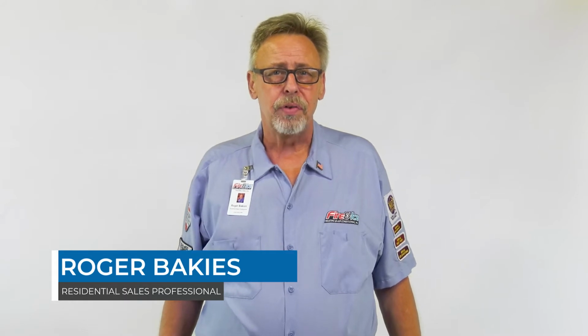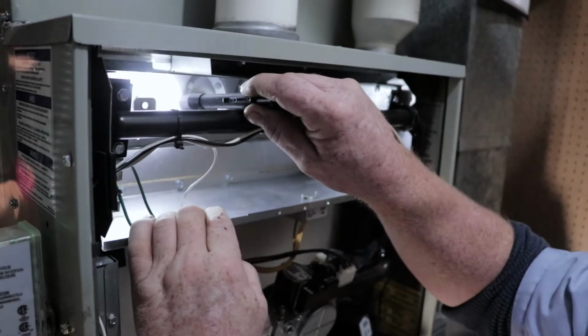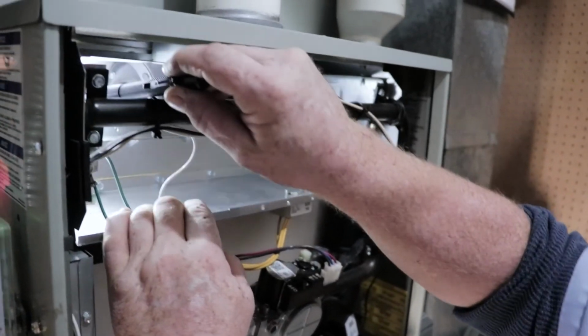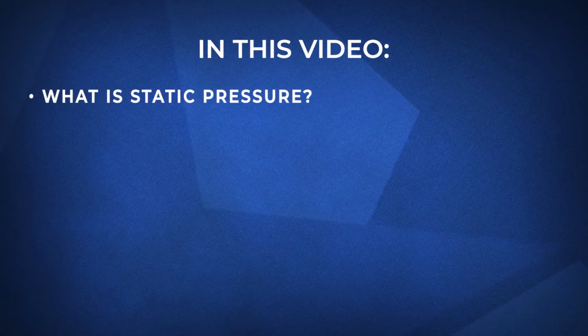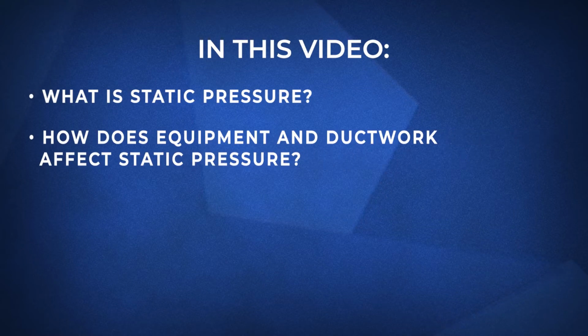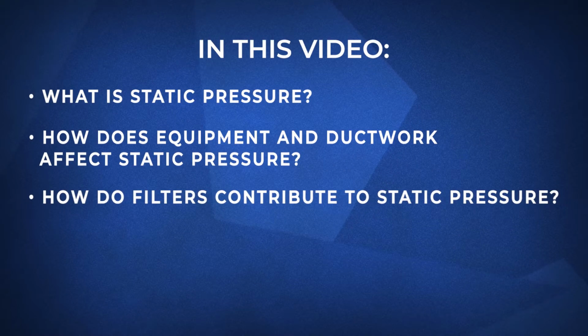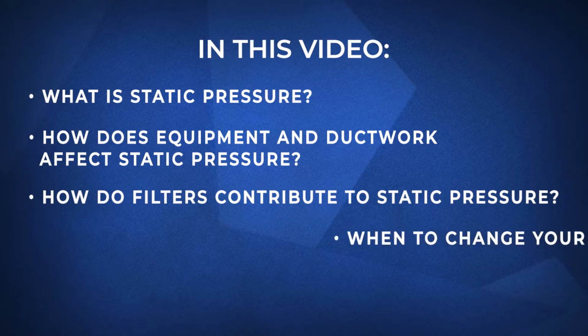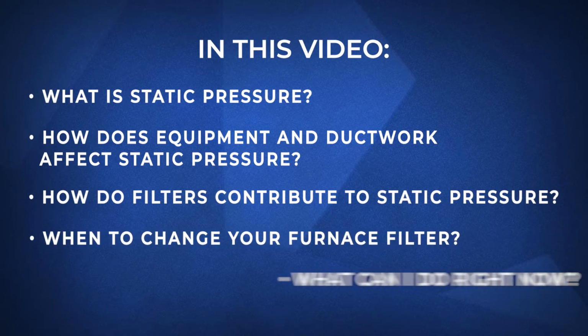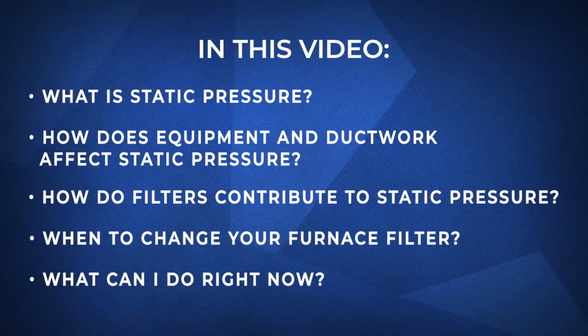Over the years, our service techs have gone out on a call to repair a system that is completely shut down. They later find the problem to be high static pressure due to a clogged furnace filter. In this video, we'll go over how a furnace filter can cause high static pressure and discuss what is static pressure, how does your equipment and ductwork affect static pressure, how do filters contribute to static pressure, when to change your furnace filter, and finally, what can you do right now?